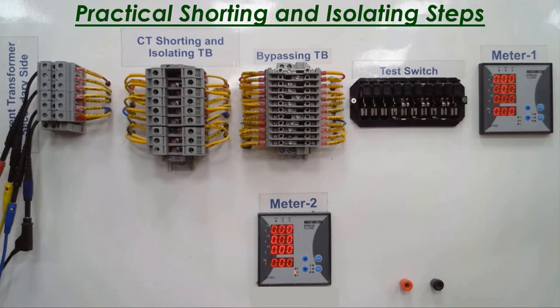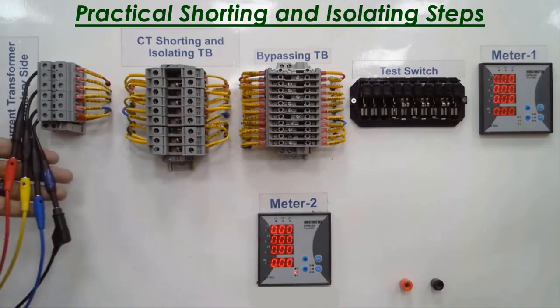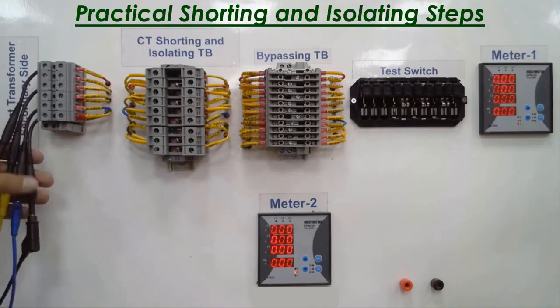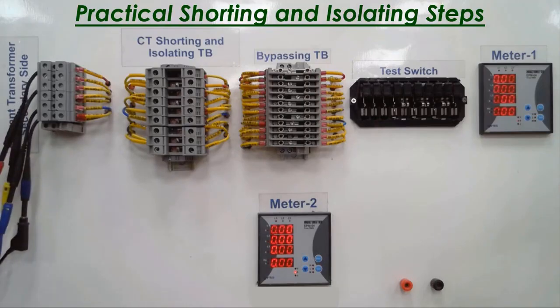Very good. Okay, at the beginning, instead of the current transformer, I will use the current generator output from any secondary injection test kit, like the Freja 300 or CMC 156. So here I have my 3 phases: red, yellow, blue, and black. Very good. Okay, now I will start injecting 3-phase balanced currents of 1 ampere on the 3 phases with a 120-degree shift between them.